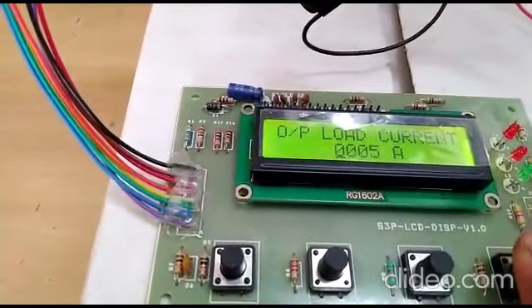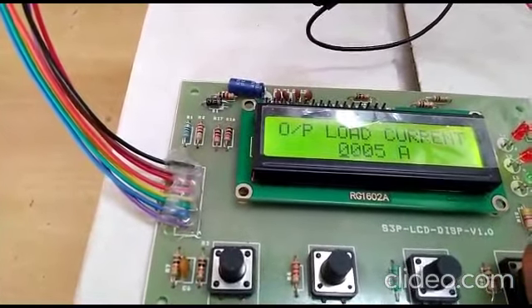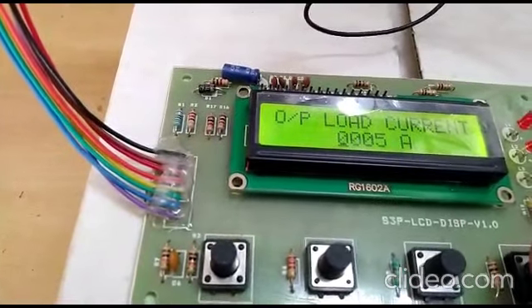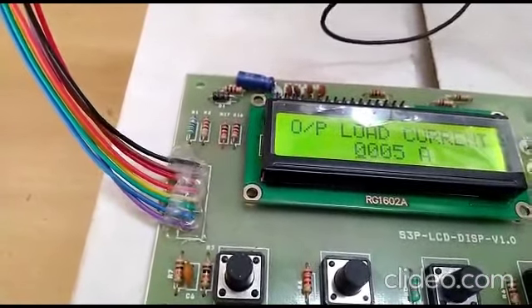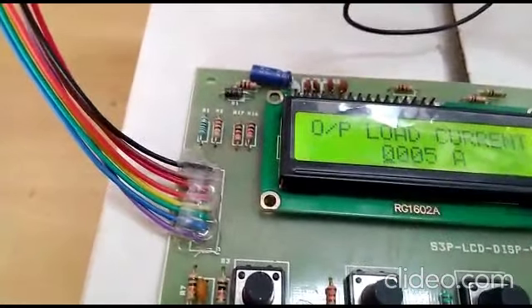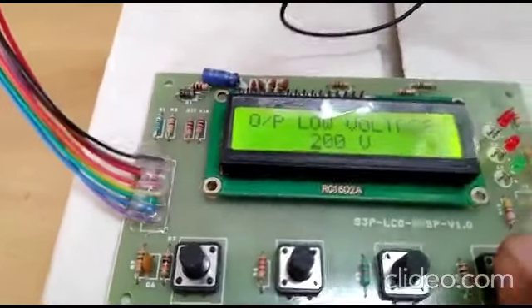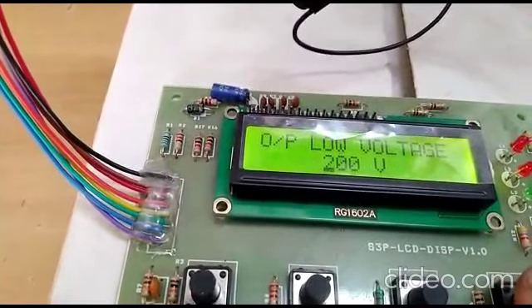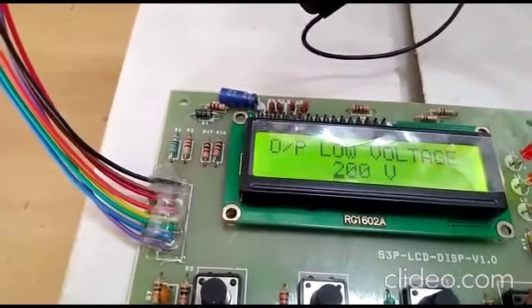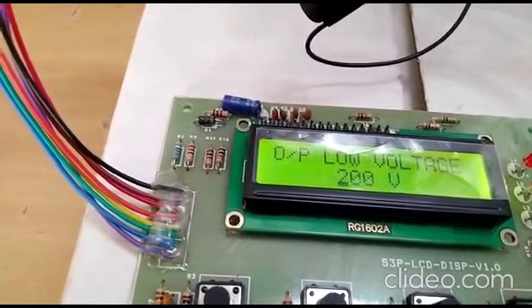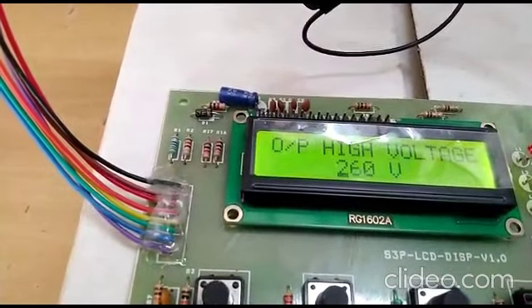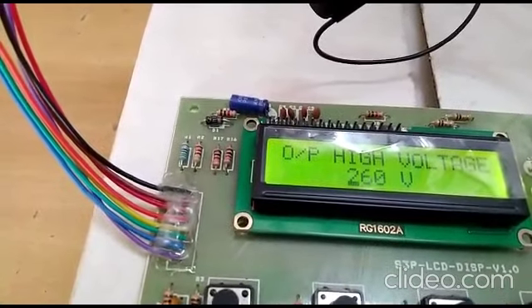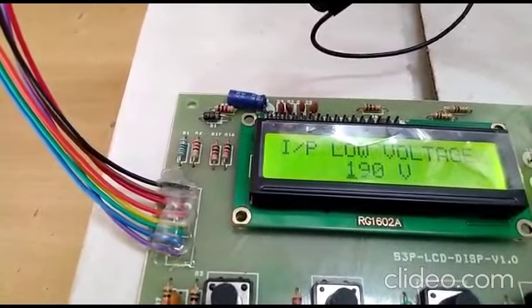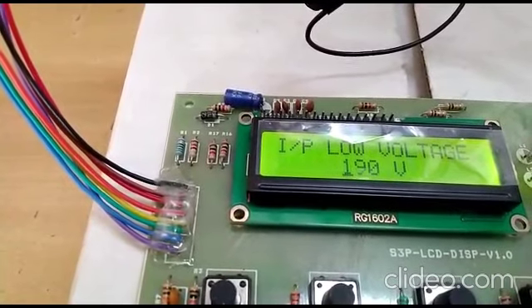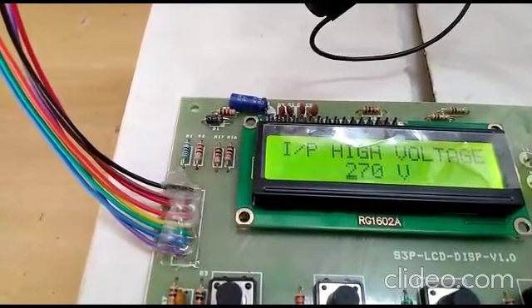The next is output load current, which is 5. The next is output low voltage. Output low voltage is 200 volts. If needed, you can change this output low voltage. The next one is output high voltage. Output high voltage is 260. The next one is input low voltage. Next, input high voltage is 270.